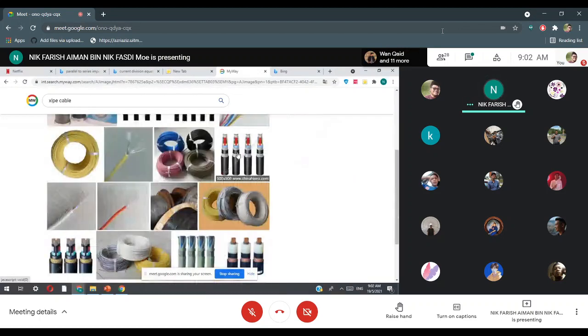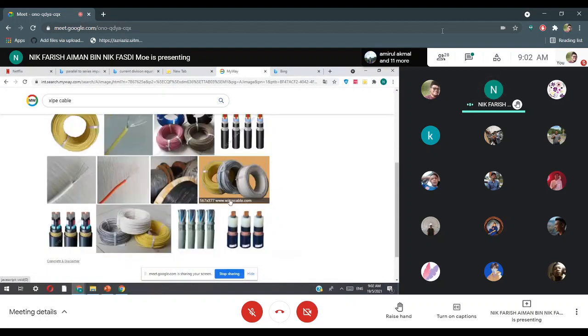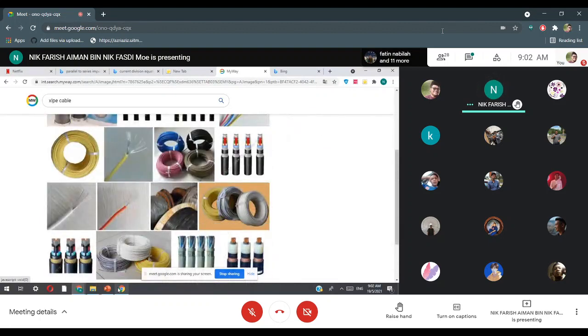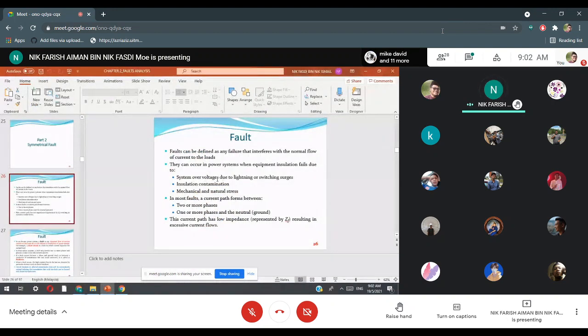Okay, ini kabel-kabel yang digunakan, contoh RYB ground. Bukan senang kabel macam ni nak orang kata fail in term of operation. Tapi because of the lightning strike contohnya, over voltage, dia boleh terbakar dan boleh open kan copper yang carry current tu to the environment, so that's very dangerous, dia boleh short dengan phase. Insulation contamination, mechanical and natural stress, mungkin sometimes orang buat construction dia terkena kabel tu boleh putus ataupun damage, so dia boleh menyebabkan fault.